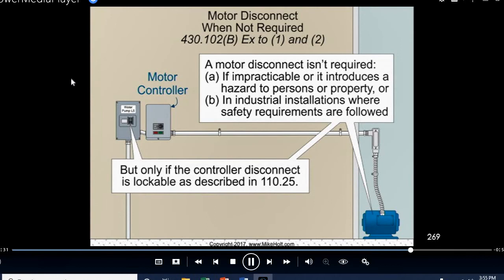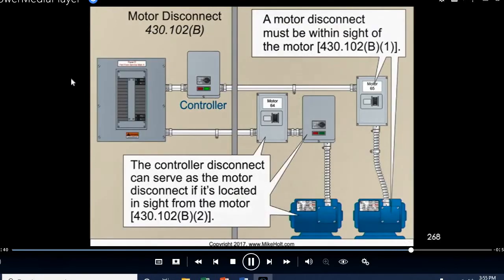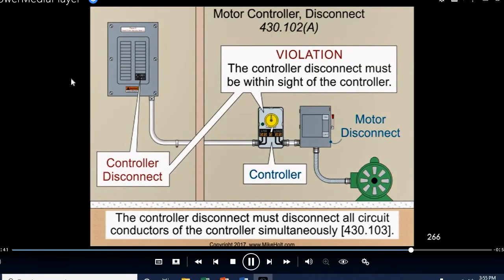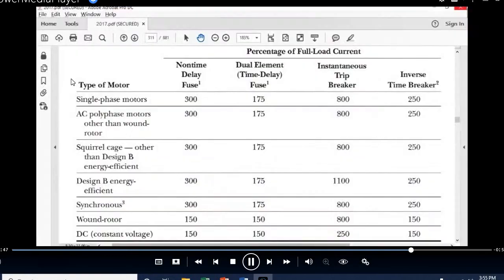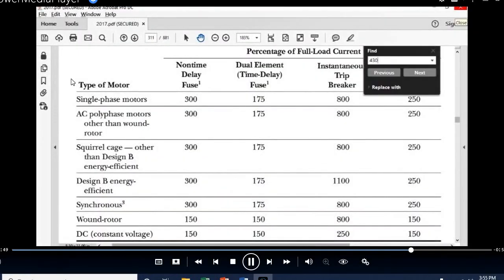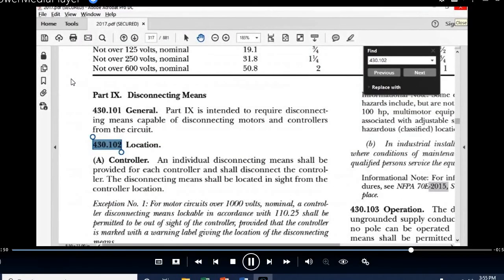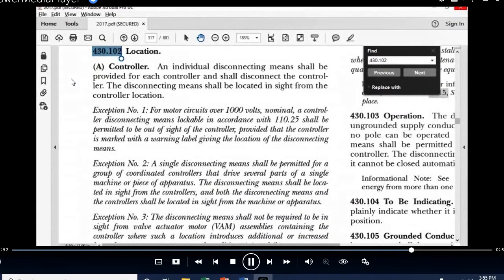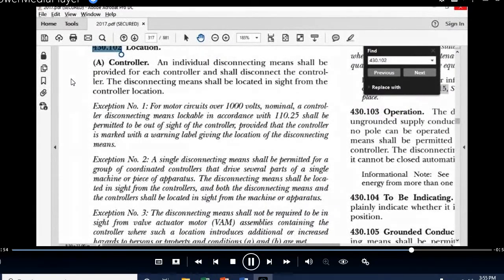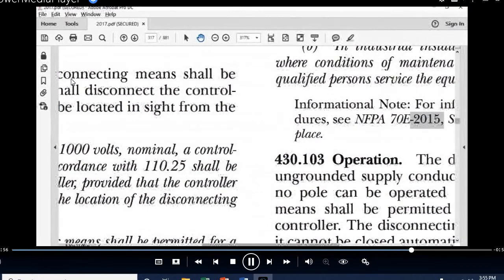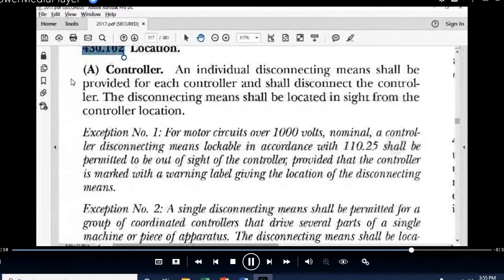Now, let's have some exceptions. I'm wondering, is there an exception for the controller disconnect? Can I have an exception that the controller disconnect doesn't have to be in sight if it's capable of being locked in the open position? 430.102. I hope that's clear as mud. What I usually do is put a disconnect at the motor.